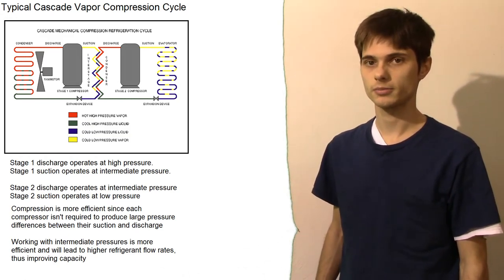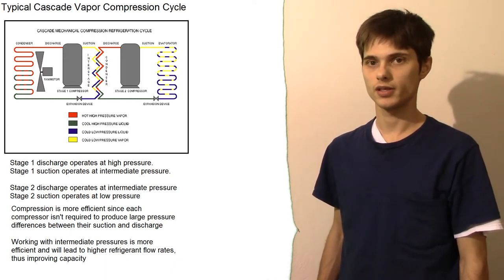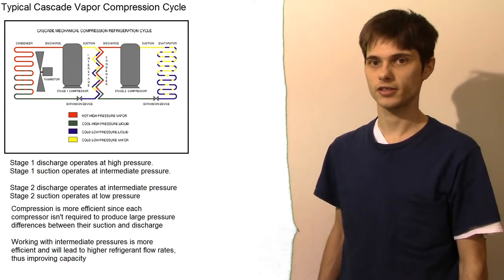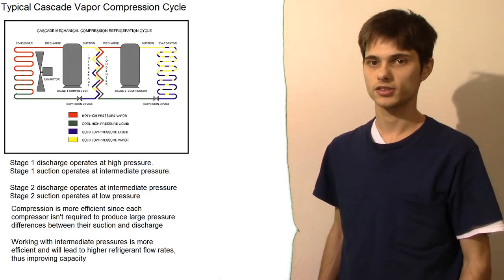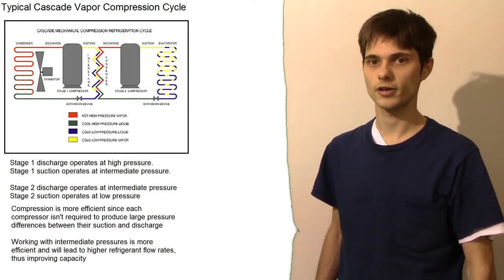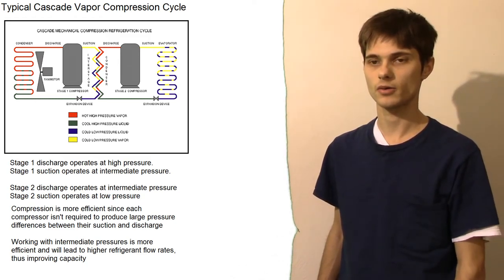Now again, on the low temperature cycle, the discharge of that will be the condenser of the low temperature cycle and that will also be in the heat exchanger. And finally, the suction side, the low side of the low temperature cycle, will be the evaporator, ultimately where heat's coming from. That will do our cooling.